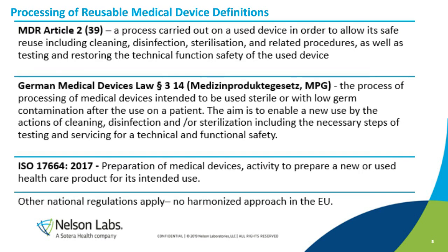Now we'll go over some of the kind of boring part of this presentation, but I want to make sure that we get through all of the definitions and so on that are very important for this type of processing of medical devices. So according to MDR, Article 2, Part 39, the process carried out on a used device in order to allow its safe reuse includes cleaning, disinfection, sterilization, and related procedures, as well as testing and restoring the technical function safety of the used device.